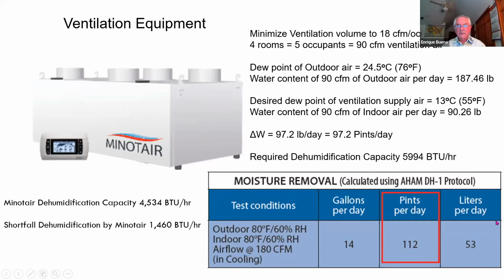But since this measurement was taken at different conditions, we re-engineered this and calculated the dehumidification capacity required for these 97.2 pints, which came up to 5,994 BTUs per hour. Then we also went back and re-engineered the Minotair dehumidification capacity from this data to 4,534 BTUs per hour. So there is a shortfall of dehumidification by the Minotair of 1,460 BTUs per hour.